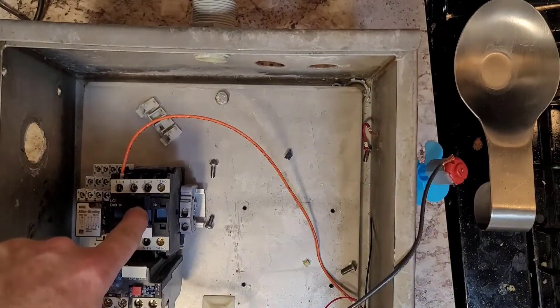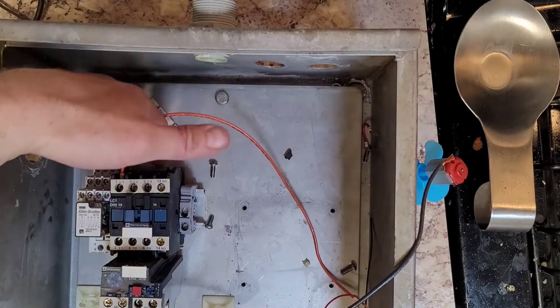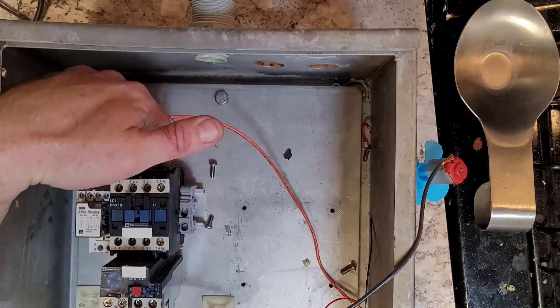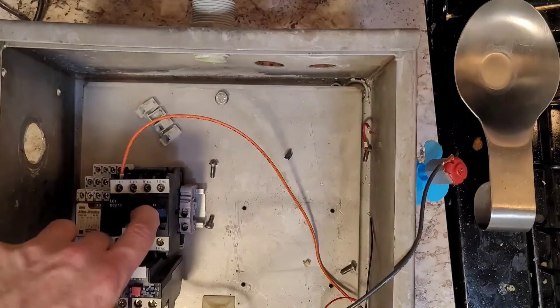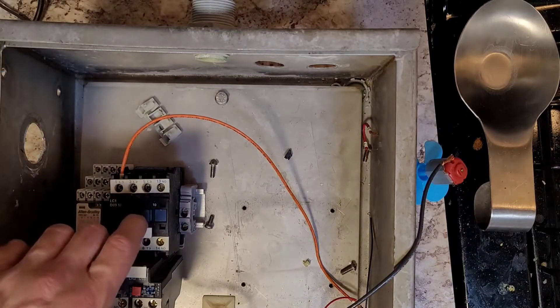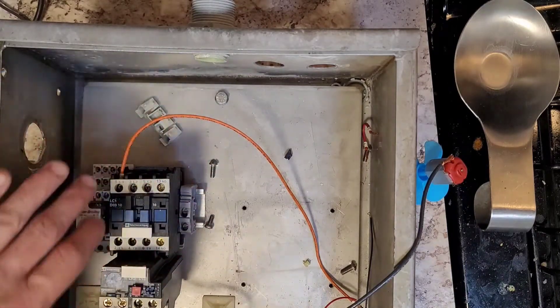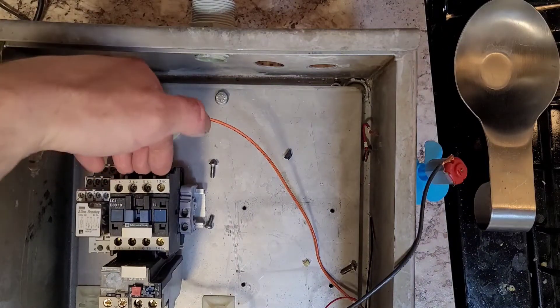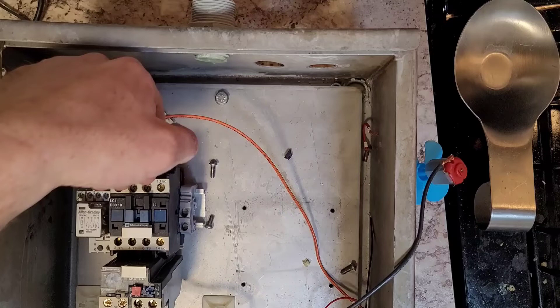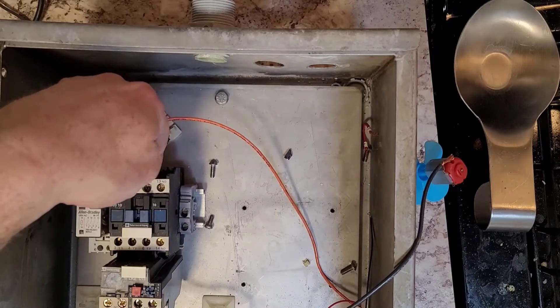This right here is the coil of our motor starter. This is a motor starter, also called a contactor. You energize the magnetic coil at A1 and A2, and when you do that it pulls in. When this pulls in, there's a set of metal contacts that closes L1, L2, and L3.